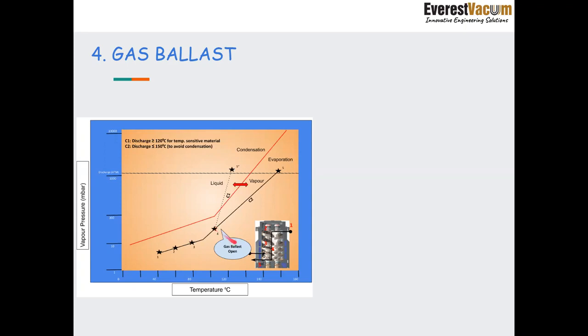Because if there is no purge of gas at stage 4, what would happen is this line from 4 will go to 5 dash. So these vapors will start converting into liquid, and we need to stop this because we do not want compression happening inside the dry screw vacuum pumps, as liquid is incompressible and it will lead to damage to the pumps, and if the liquid does not go out properly, it can create back pressure and damage the pump. So at point 4, we purge a small amount of gas. It increases the temperature and keeps the vapor in the vapor phase itself.